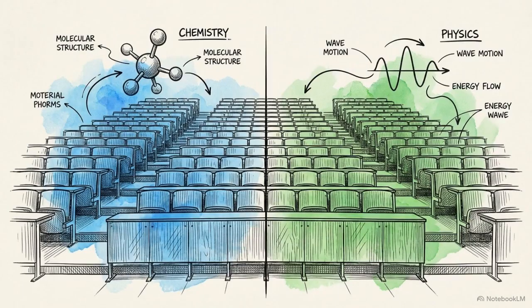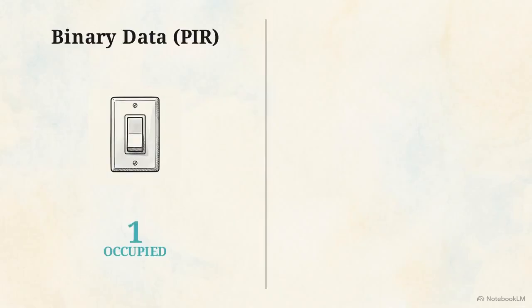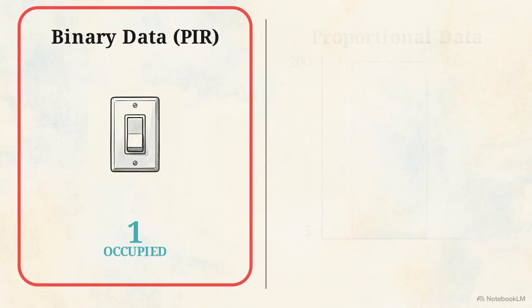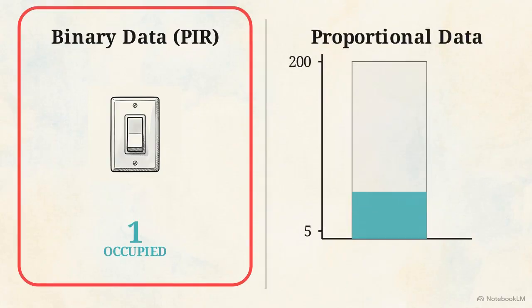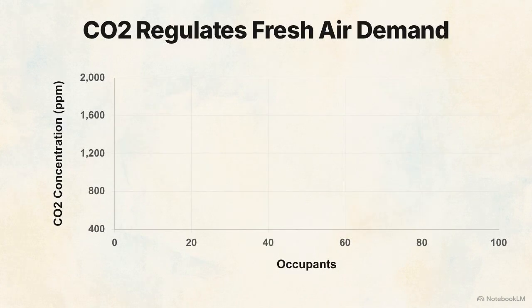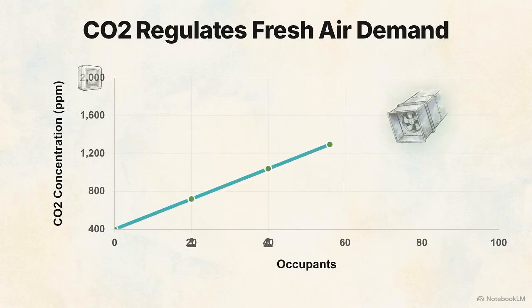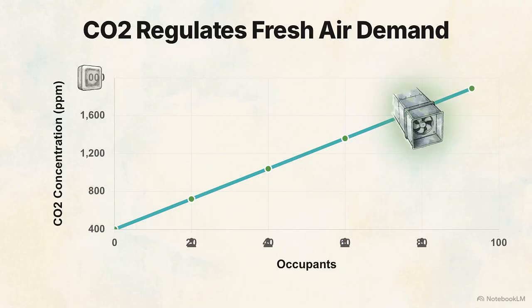Finally, look closely at question 7, which requires choosing between CO2 and PIR sensors for demand-controlled ventilation in a massive lecture hall. Here is the trap. PIR motion sensors provide binary, yes or no data on presence. That is the wrong kind of data for a space that scales dramatically from 5 people to 200 people. CO2 is the correct answer. It provides proportional data, telling the system exactly how many people are breathing in the space, which accurately dictates how much fresh air is required.